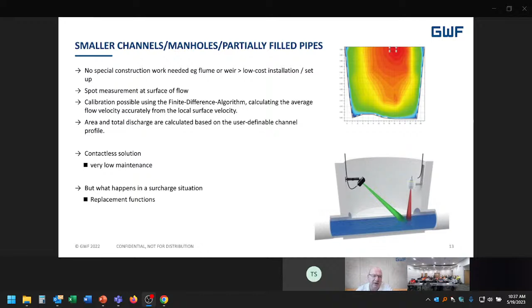So what happens if you don't quite have the heavily polluted media? What other options are there? There are several area velocity sensors out there. Using Doppler technology, they're able to look at the velocity of the flow, and many of them have a built-in level sensor, or have the capability to allow an external level sensor to be used as well. Some systems even allow both, so you have a backup. What does this mean? If there's an issue, or the flow's in a very large channel and you reach the limit of the built-in level sensor, it will switch across to an external one and keep measuring.